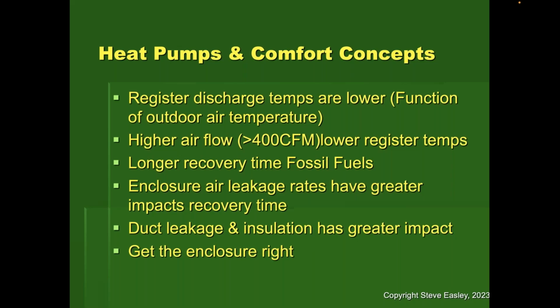More, I guess, a representation of a better real world efficiency. So the bottom line is the comfort concepts we want to remember is that with heat pumps, register discharge temperatures can be lower, which can be a function of outdoor air temperature. Not necessarily the case with inverter driven. It will be a little lower, but certainly can be. Higher airflow means lower register temperatures. So in other words, if we have more than 400 CFM, cubic feet of air per minute, you might tend to have lower register temperatures.